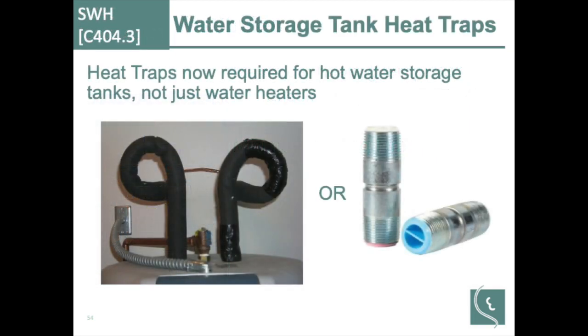Storage water heaters. Heat traps are now required for hot water storage tanks, not just water heaters. And the heat trap is just this little piping loop, keeps you from having convective water flow due to differential temperature of the water. And that is a change for plumbers. The plumbing code, I don't think, includes this in it. So it's something the energy code adds on top of the plumbing code. So that's something to be aware of for plumbing contractors, is that if they're following the plumbing code, they'll also have to reference the energy code to know that to install these.